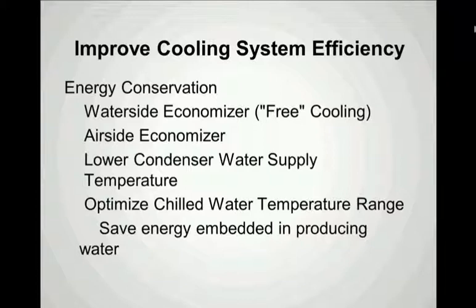If your building is equipped with air-side economizers, using them when outside air temperatures are appropriate again takes the load off the chiller, but also has the added benefit of taking some of the load off the cooling tower — so it not only saves energy, but also saves water. Operating the cooling tower to produce the best possible condenser water temperature also saves energy.